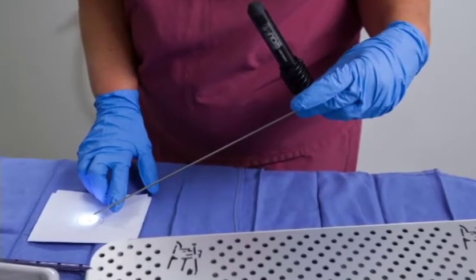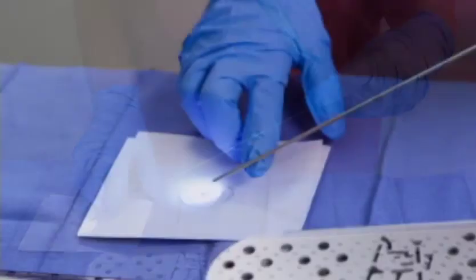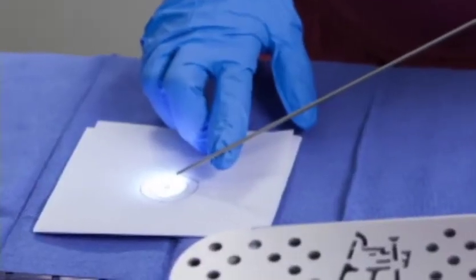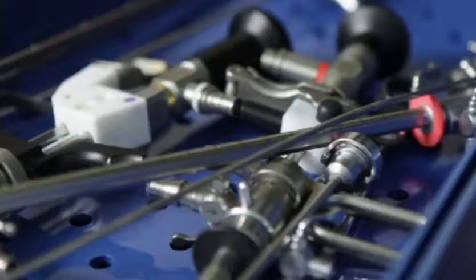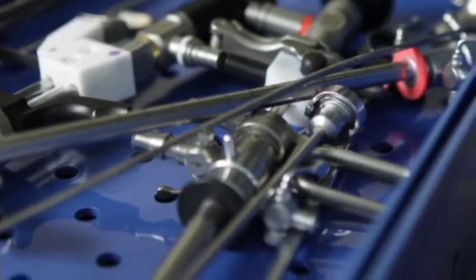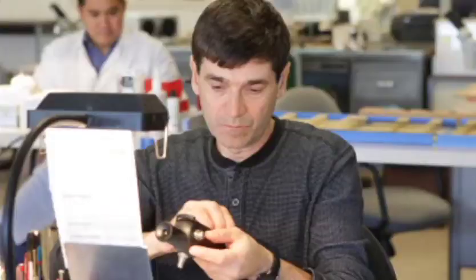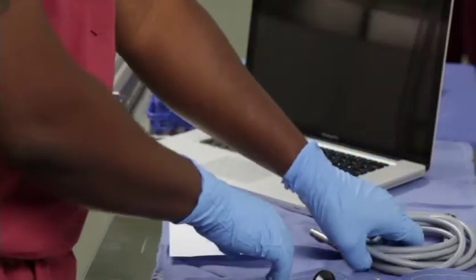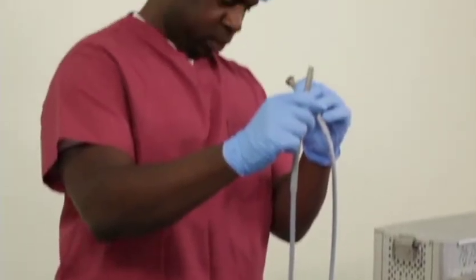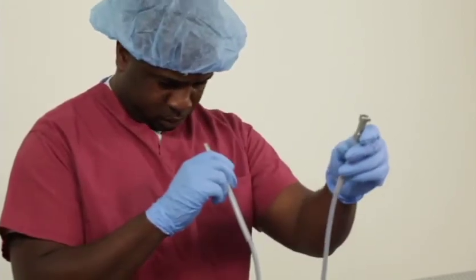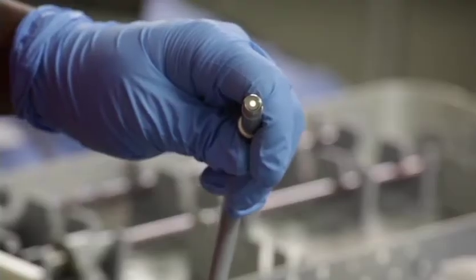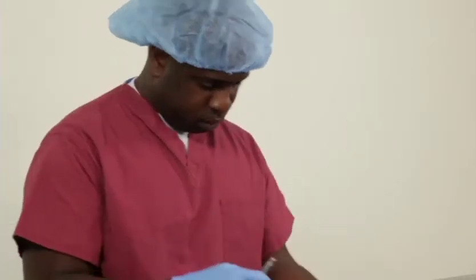A portable light source, like the one shown here, can also be used to check the scope's light fibers. If more than 30% of black spots appear in the light post of the scope, send the endoscope for repair. Clean and sterilize the endoscope before sending for repair. Next, inspect the light quality of the light cable. Hold both ends up to a ceiling light. Both ends of the light cable should appear milky white with no black spots.